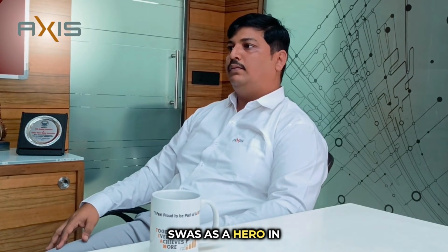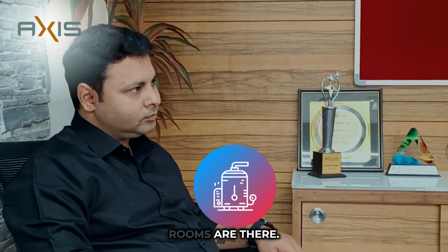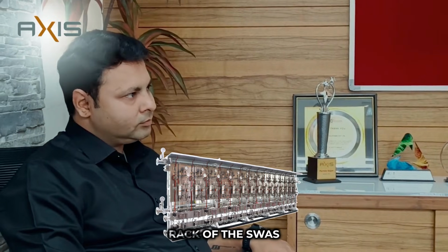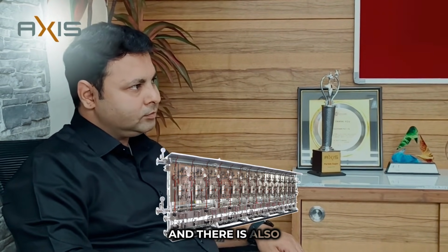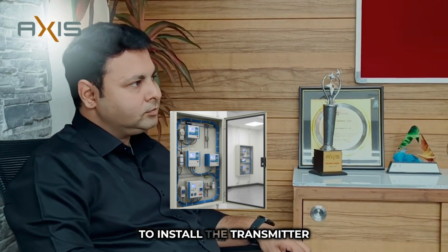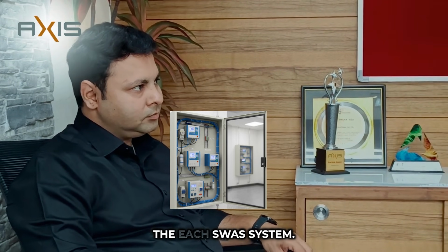So you talked about power plant and you talked about SWAS as a hero in the power plant. Right. So where exactly is SWAS installed in the plant? Okay. We can install SWAS near the boiler room. In every boiler there are SWAS rooms. We take the samples from the boiler and give them to the wet rack of the SWAS panel, and there is also a dry panel available where we install the transmitters or analyzers for each SWAS system. So we are talking about the dry and wet panel.